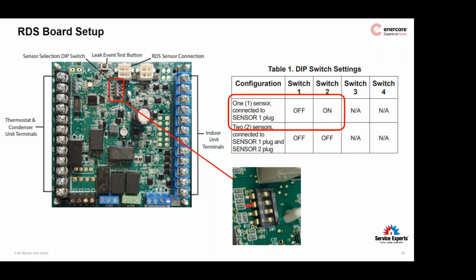When you first power up the RDS boards, during initialization, which is about 5 minutes, they will go through a purge sequence and self-detection sequence, looking to verify that you've connected your 1 or 2 sensors and that the system is basically connected correctly. It'll identify any potential errors and flash a code if there are any errors during the initialization portion. We'll go over those codes shortly.